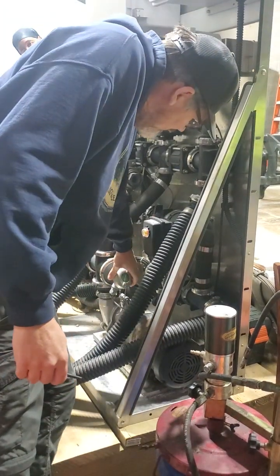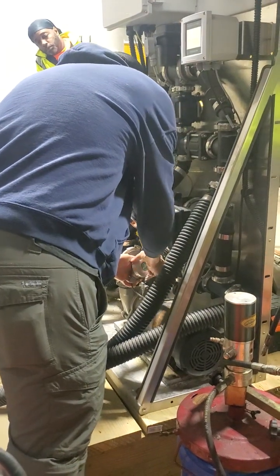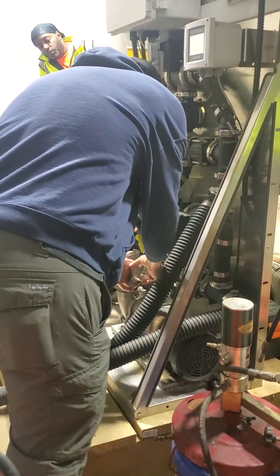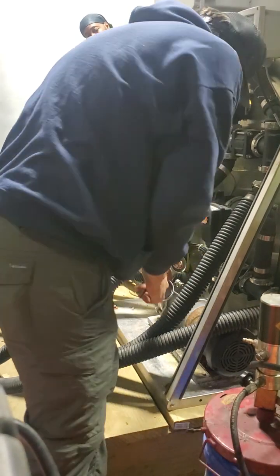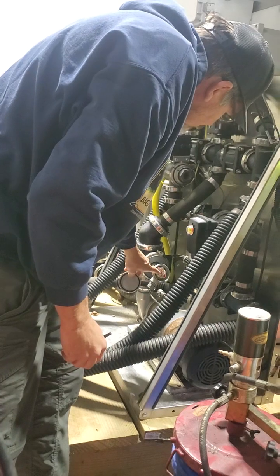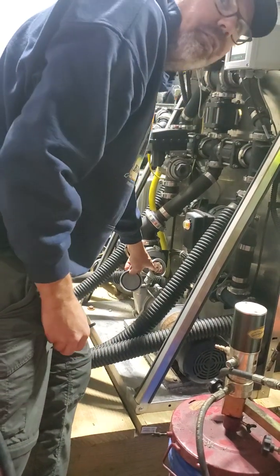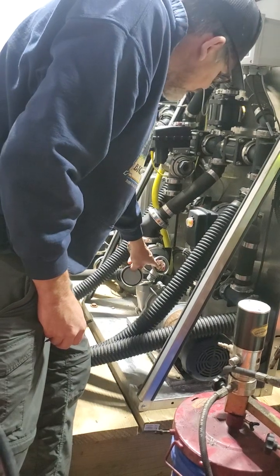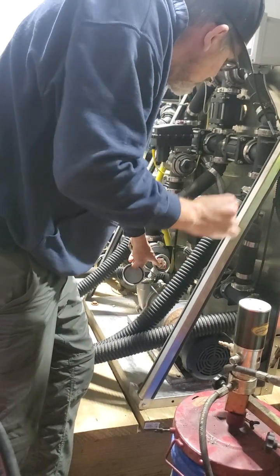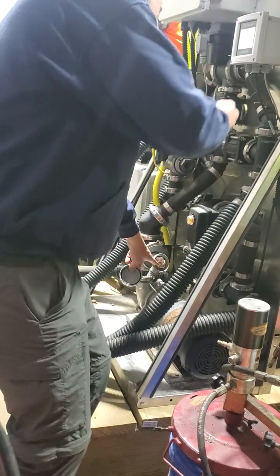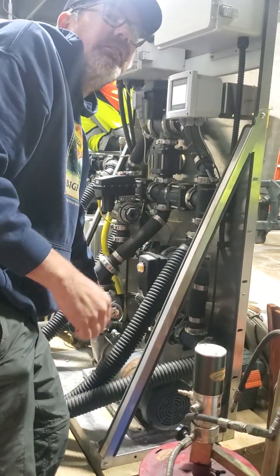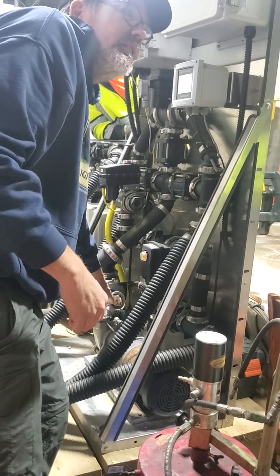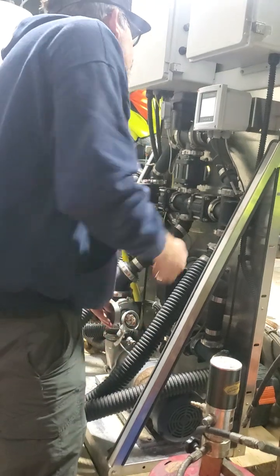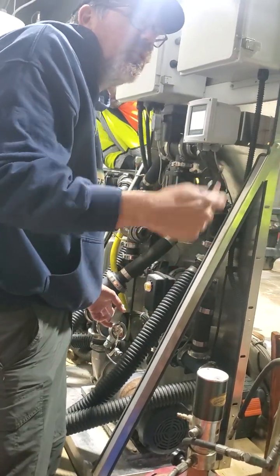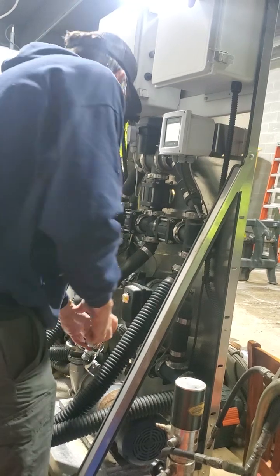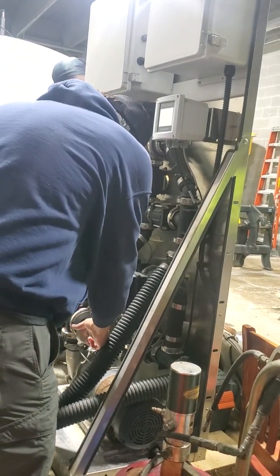What will happen if I take this cap off? These little wires, just due to vibration over time, I've seen them break off inside their little housing. They'll sit there and intermittently stop giving a signal, and it'll cause the temperature to spike to like 300 degrees or something. So it's just something to look for. If the brine's not getting concentration, come back here and look at the temperature. I've seen it 3 or 4 times, so it's definitely worth telling you about. These wires only have about 3 strands of copper in them.